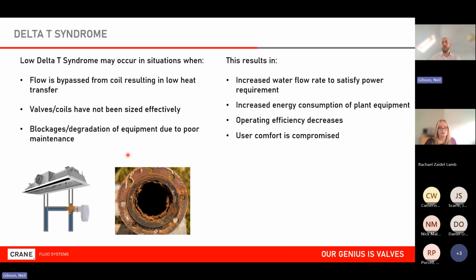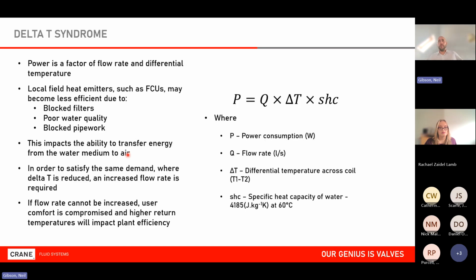We could have blocked coils over time as well, and all of these lead to this delta T syndrome. Now, what does that mean? If we have a reduced delta T, in order to generate the same power, the only thing I can really do is increase flow rate. Now, this is critical to the next part, because as I increase flow rate, I'm obviously generating more energy as well from the pump, and from the power required there, just to achieve the same heat output to the user, assuming specific heat capacity is a constant anyway. So it's only a factor of Q, flow rate, and delta T.